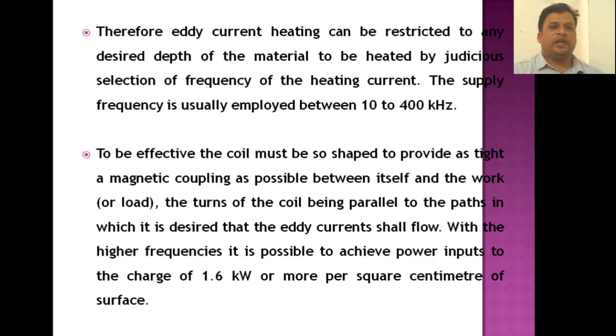Therefore, eddy current heating can be restricted to any desired depth of the material to be heated by judicious selection of the frequency of the heating current. The supply frequency usually employed is between 10 and 400 kilohertz. This is the type of frequency we employ for desirable heating.